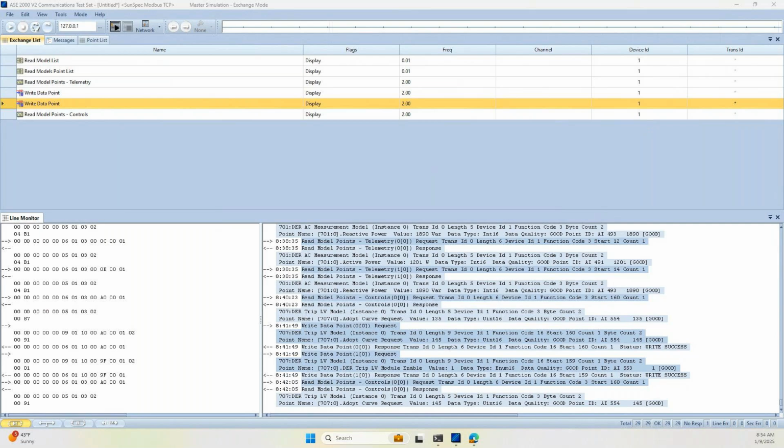Then the next question I see is: how reliable is monitoring and controlling the remote station field equipment? Generally, these connections, as I mentioned earlier, are managed by the site gateway over cellular links. The cellular connection mode is used by the site gateway to establish connection with the DERMS, and DERMS will continuously get updates like telemetry updates from the field devices. Because of 5G networks across the world, you can see that it's a pretty reliable communication.